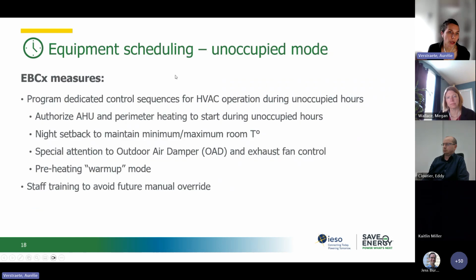For that case, the measure would be to program dedicated control sequences for HVAC operation during unoccupied hours. So yes, we can authorize the air handling unit and perimeter heating to start during unoccupied hours, just to maintain minimum and maximum room temperature indoors. But you will pay special attention to the outdoor air damper and exhaust fan control. The air handling unit should be on recirculation and the exhaust fan should be stopped at night. You can also program a preheating or warm-up mode, for example, to authorize outdoor air admission maybe only 30 minutes prior to occupancy. And finally, you want to train staff on those capacities to avoid future manual override.